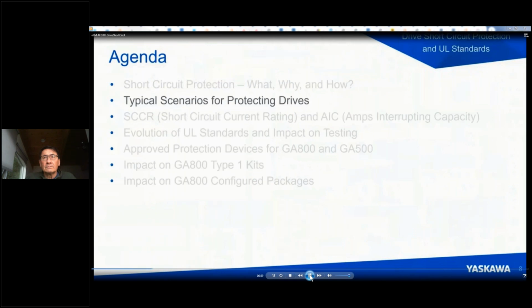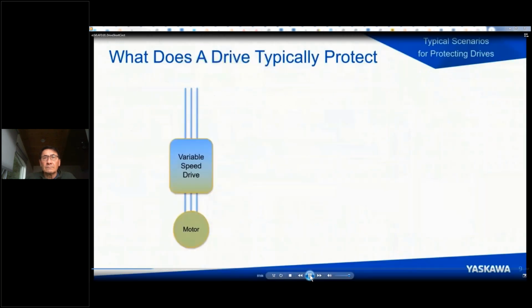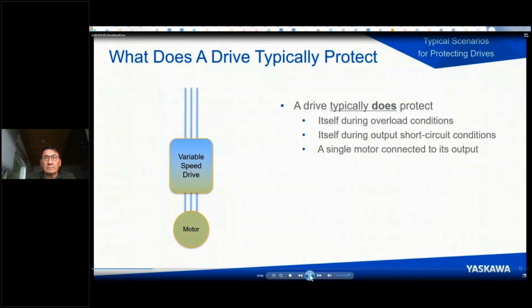Okay, next, let's talk about some typical scenarios for protecting drives. First, what does a drive by itself typically protect? Well, it typically protects itself during overload conditions. It typically protects itself during output short circuit conditions, that is, a short between the drive and the motor. The drive will protect itself against that kind of a condition. And then in addition to that, it's protecting the motor, that is a single motor connected to its output.